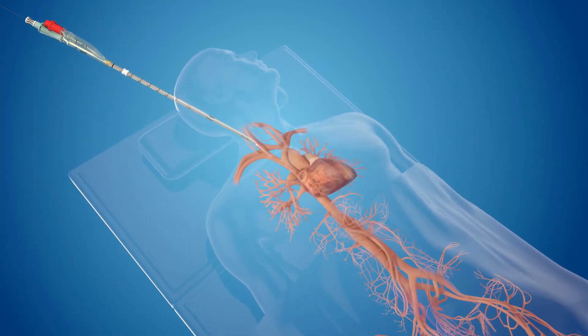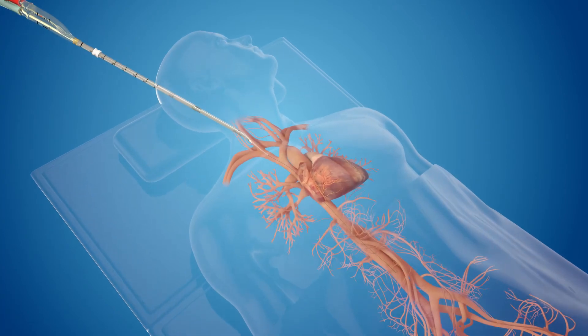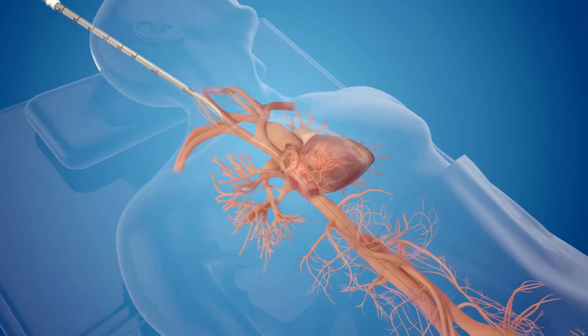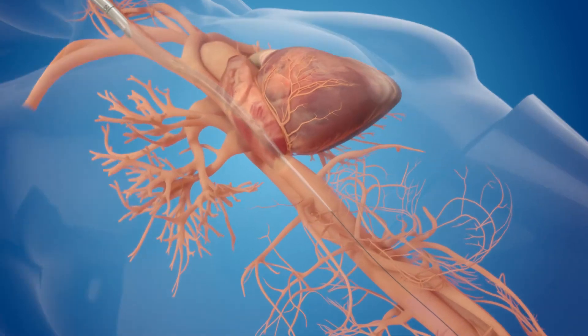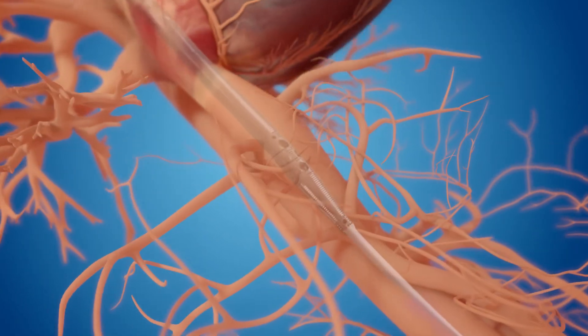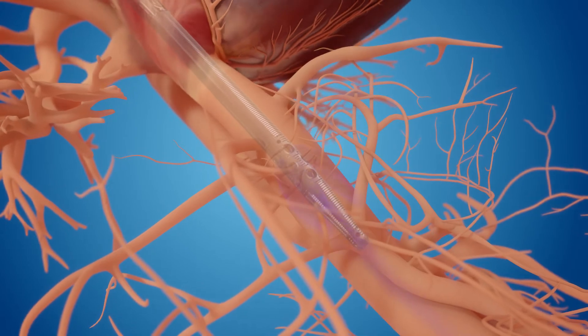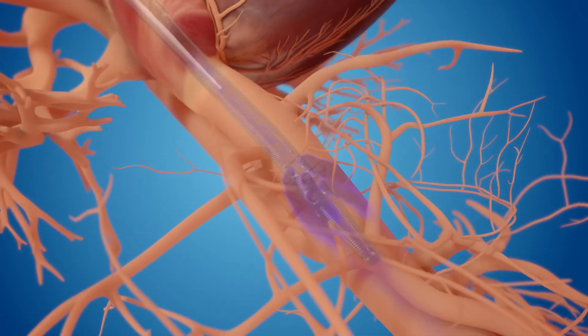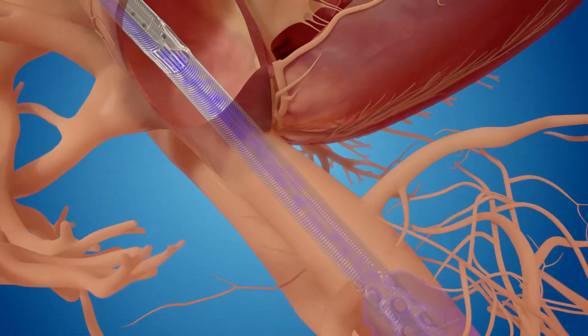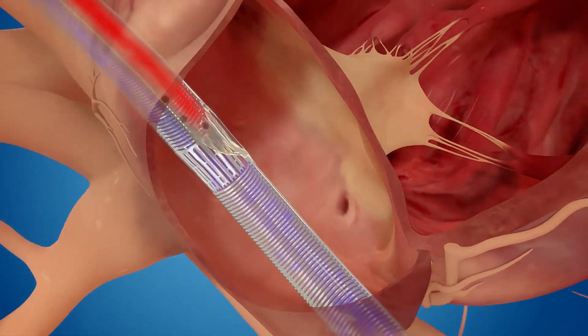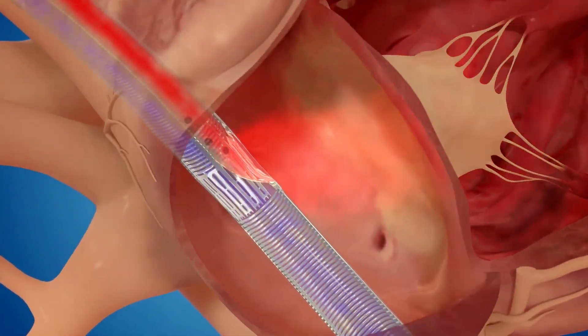The Crescent is inserted in the internal jugular vein. It is supplied with an introducer to facilitate wire-guided placement into the vasculature via a Seldinger-type approach. The bicaval design drains venous blood from both the inferior and superior vena cava while reinfusing oxygenated blood into the right atrium.